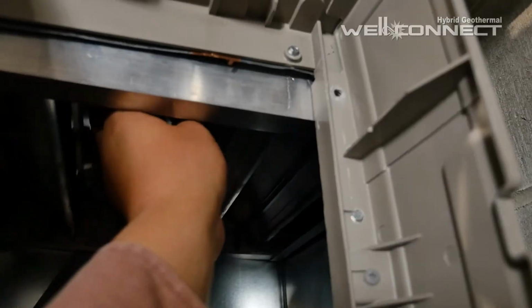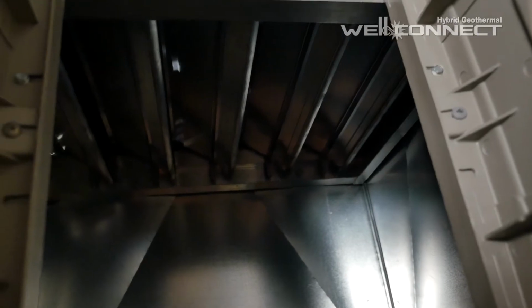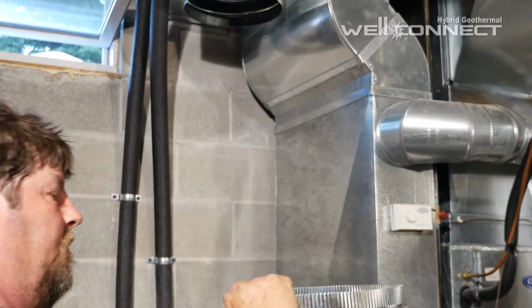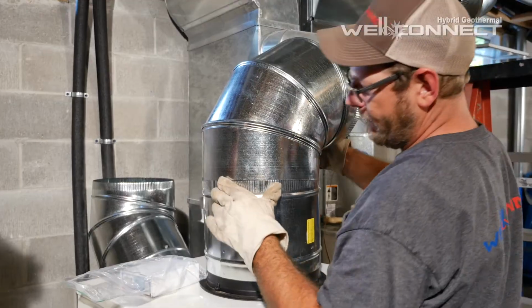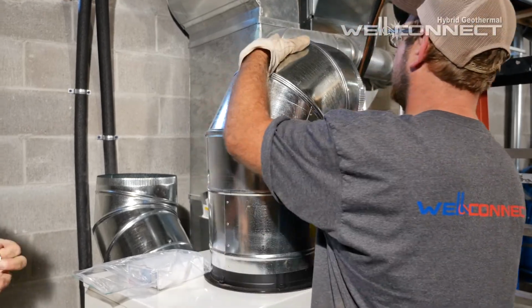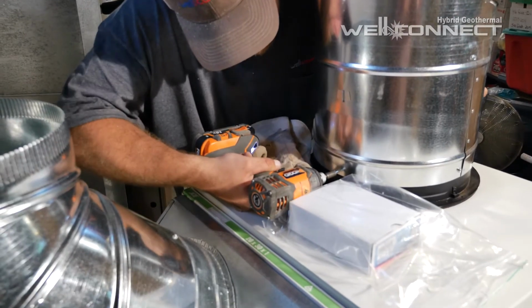To enable this, there must be a backdraft damper placed in the air supply plenum of both the Well Connect and the furnace. The Well Connect comes with a 12-inch round butterfly-type backdraft damper that is simply placed over the 12-inch start collar on top of the Well Connect and secured with a couple of zip screws.